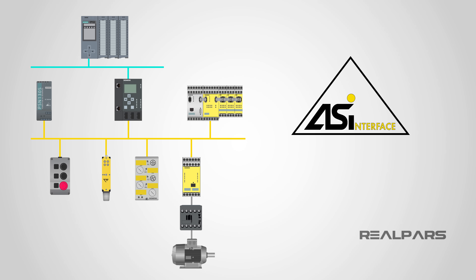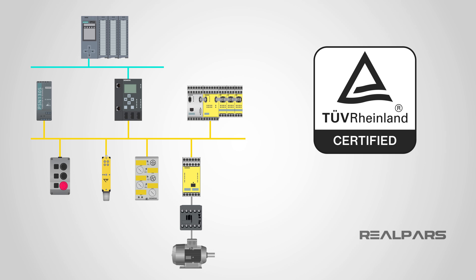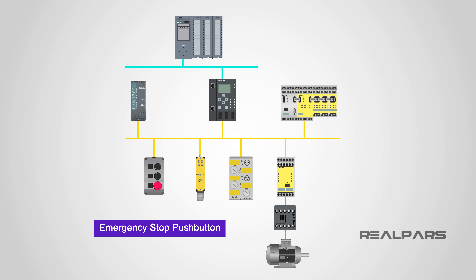AS Interface can also be used in safety systems. ASI Safe, or ASI Safety at Work, is a standard AS Interface network but with special ASI Safe components. An ASI bus system is TUV certified up to performance level E, or PL-E, or Safety Integrity Level 3, or SIL 3. An advantage of ASI Safe is that components can be connected directly to the AS Interface network, such as emergency stop push buttons or safety door contacts.